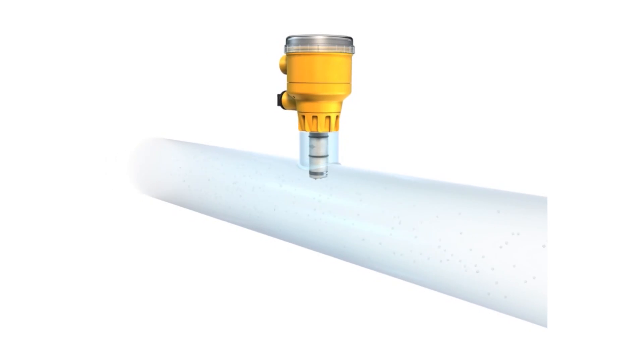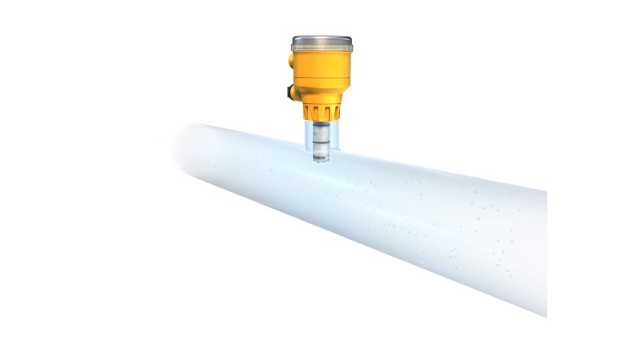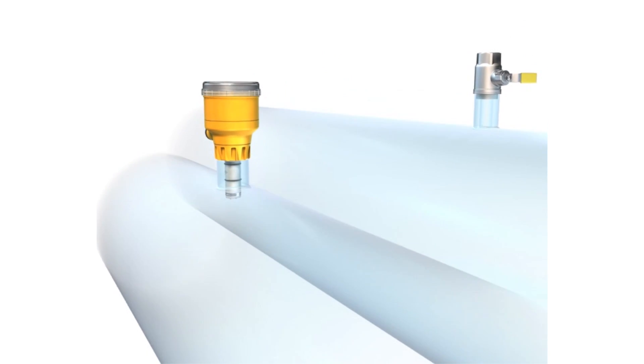Signet magmeters feature bidirectional flow and empty pipe detection and measure flow ranges from 0.15 to 33 feet per second. The 2551 is available for pipe sizes up to 12 inches.